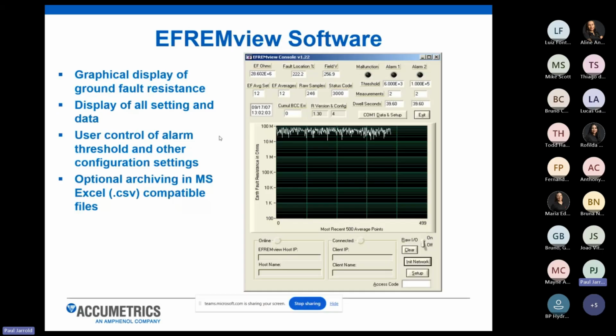You can make some changes. You can change the threshold alarms to different values. If you wanted to increase your warning alarm value to say 200 kiloohms, you can do that. You can increase your ground fault alarm larger than 2 kiloohms. Some of our customers have chosen values like 50 kiloohms for the warning and 20 kiloohms for the ground fault. So we have the ability to change the thresholds of those alarms in the software.